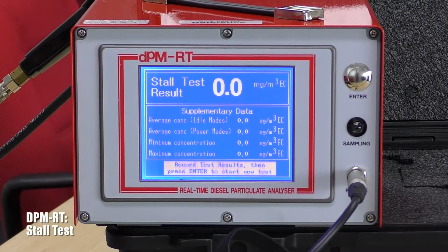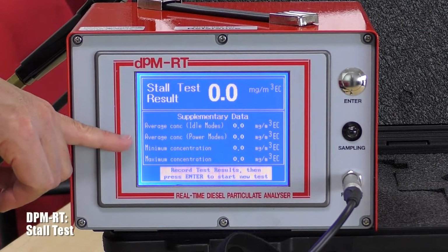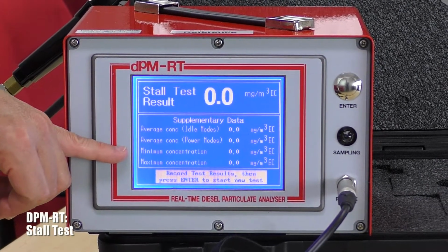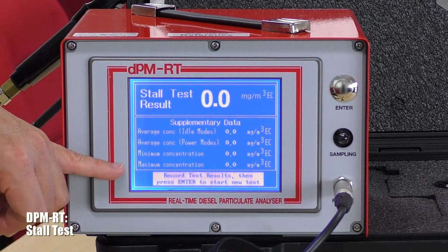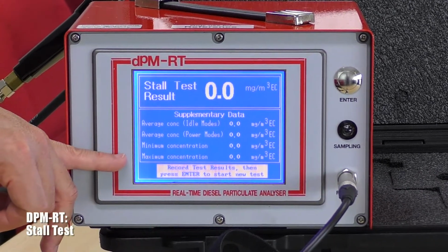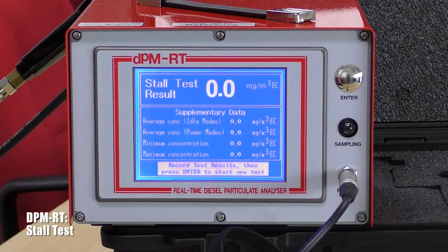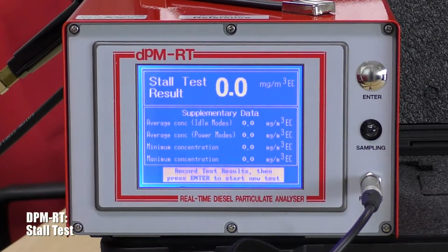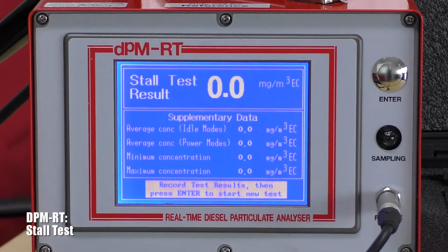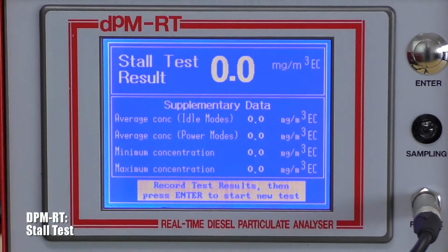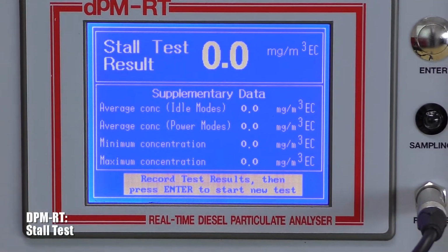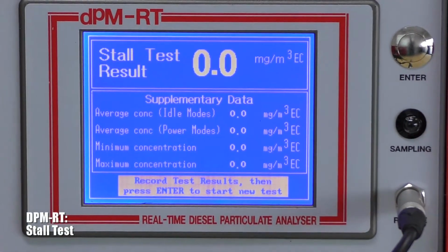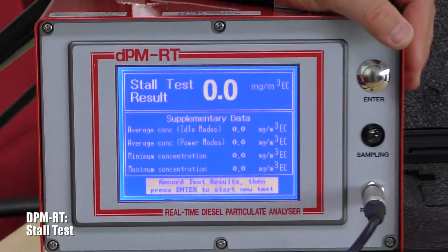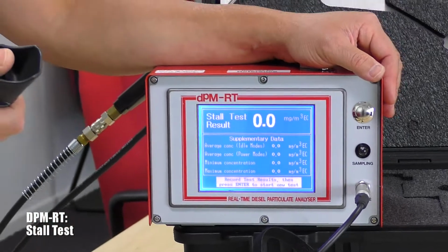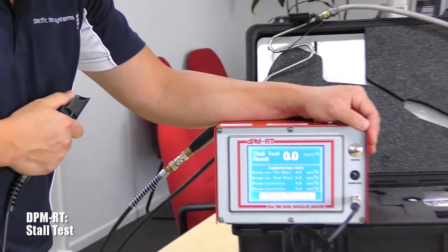Again, supplementary data: the average concentration in idle mode, the average concentration in power mode, the minimum concentration and the maximum concentration, and all of those values are in milligrams per cubic metre, reference to elemental carbon. One thing to note, when you are conducting the stall test, ensure that the transmission is engaged with the vehicle. If you want to restart the test, you can select the enter button in the remote control as per previously instructed.